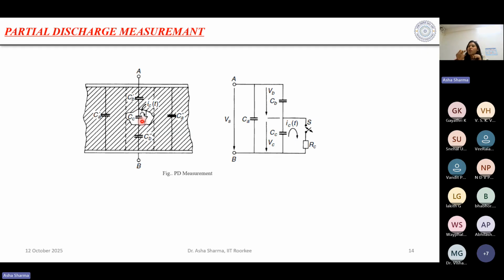What is meant by the discharge? It means obviously some current must be flowing across these two, right? If some current is flowing, how does the current flow? It is the flow of electrons, right? So obviously there will be a flow of electrons, which means there is a flow of charge. So in the measurement technique, what do we say? We can measure or see this partial discharge if I am able to measure the charge which is getting lost during the discharge phenomenon. So the whole PD measurement technique is actually measuring the charge lost within this cavity or the void or the defect, right?